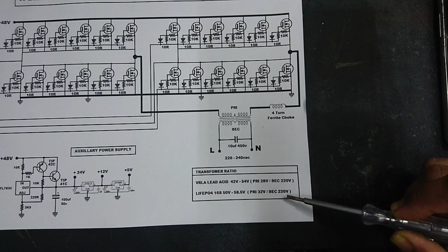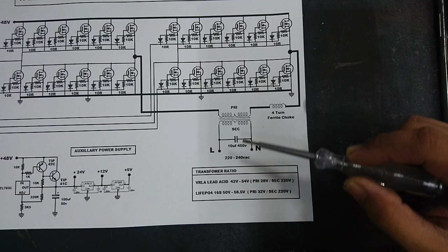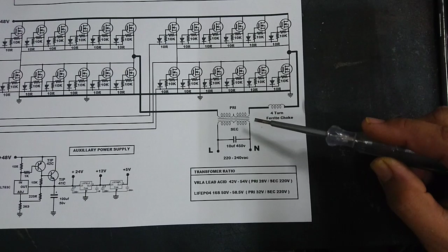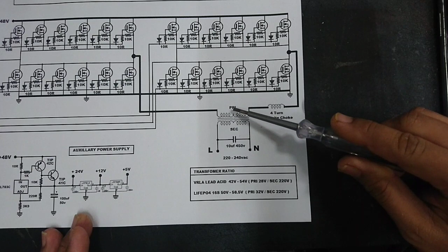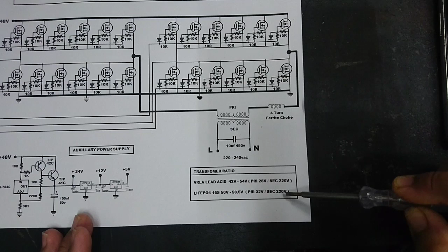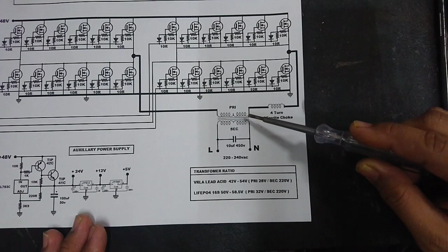Why 32 volt? Because the voltage is high for the LiFePO4. If you use the lead acid ratio for LiFePO4, you will get low efficiency in your inverter, and the transformer will get hot because the voltage is high. So your efficiency will drop to 85 or 82%. If you use the primary 32 volt, your efficiency will rise to a good 88 to 89%. 32 volt primary and secondary is 220 volt. So before design, you need to see your battery type first and design your transformer.